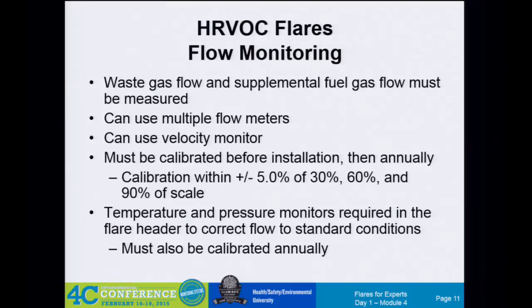One of the little nuances is where that supplemental gas gets put in and how you monitor for it. They specified some things that aren't specified in other rules. With the supplemental gas flow, your flow meter doesn't have to be in a spot that measures everything. You can have one flow meter for the vent gas and another flow meter on the supplemental fuel. You can use just a velocity monitor. You can see here the calibration requirements are a little more robust than other places. But it has temperature and pressure monitors to correct everything back to standard conditions, which pretty much everybody's comfortable with.